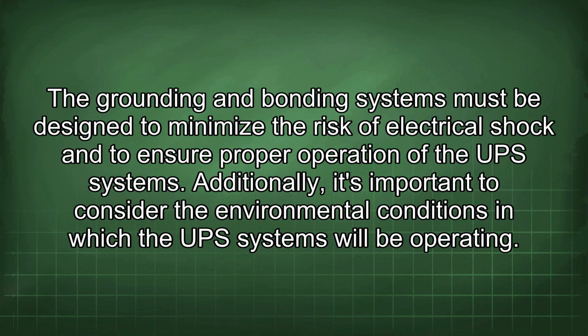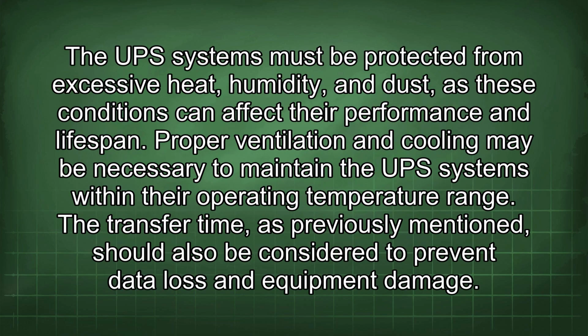The grounding and bonding systems must be designed to minimize the risk of electrical shock and to ensure proper operation of the UPS systems. Additionally, it's important to consider the environmental conditions in which the UPS systems will be operating. The UPS systems must be protected from excessive heat, humidity, and dust, as these conditions can affect their performance and lifespan. Proper ventilation and cooling may be necessary to maintain the UPS systems within their operating temperature range. The transfer time, as previously mentioned, should also be considered to prevent data loss and equipment damage.